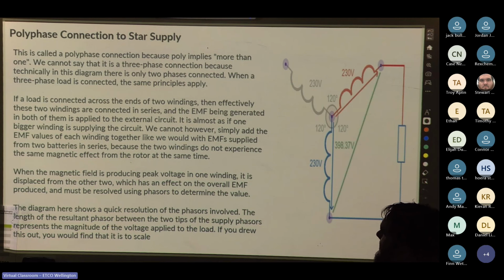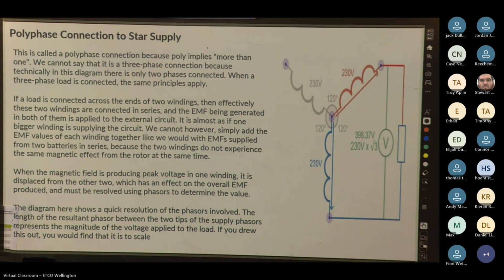So it's a polyphase connection. We cannot say that it's three-phase because we haven't connected it to three phases. But the same principles apply in terms of voltage level. If we were to connect the load, EMF being generated, and both of them apply to the external circuit, it's almost as if one bigger winding is supplying the circuit. But we can't just add the EMF values.